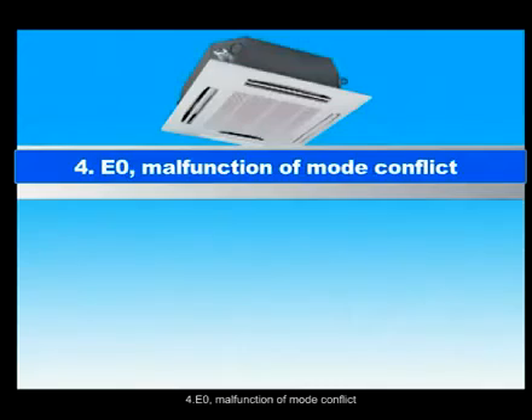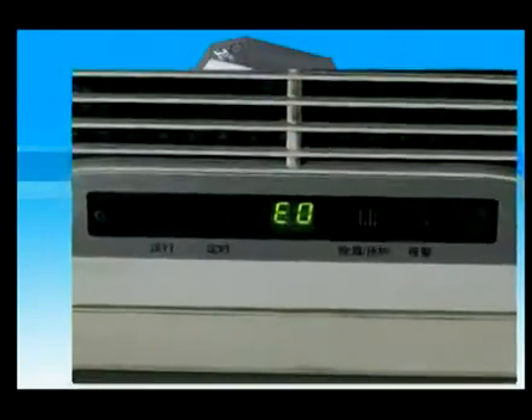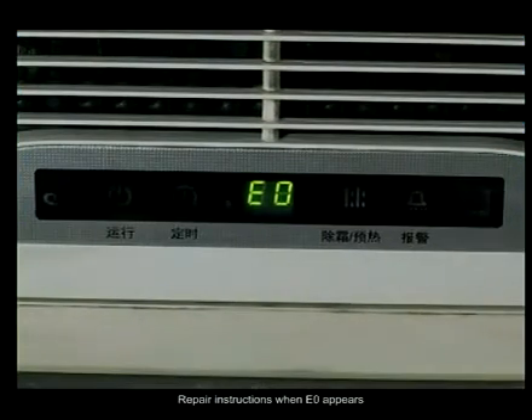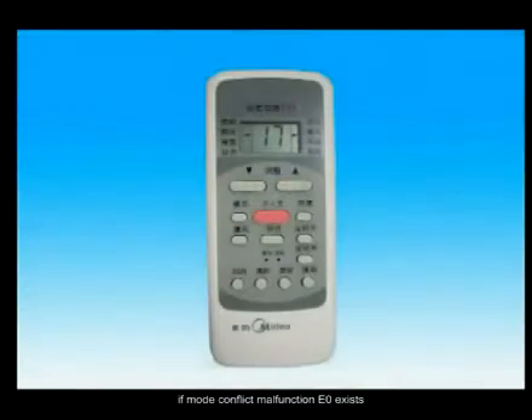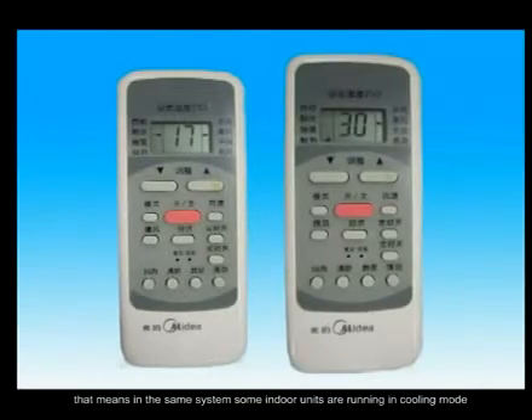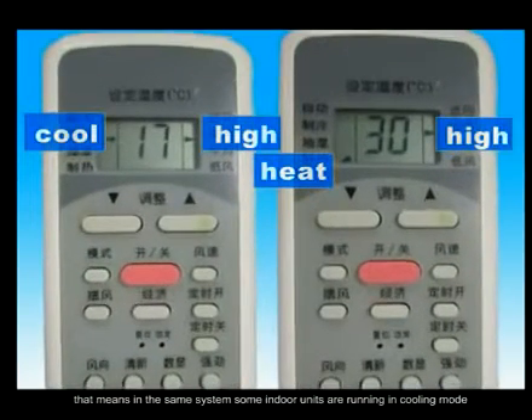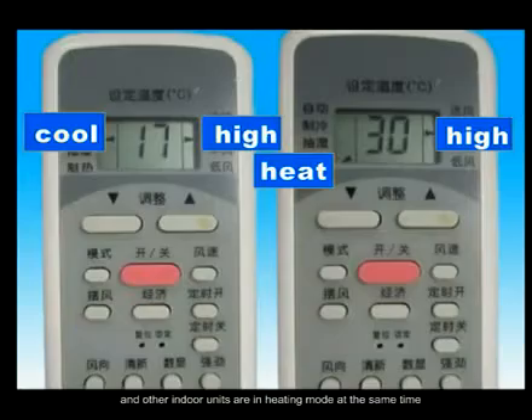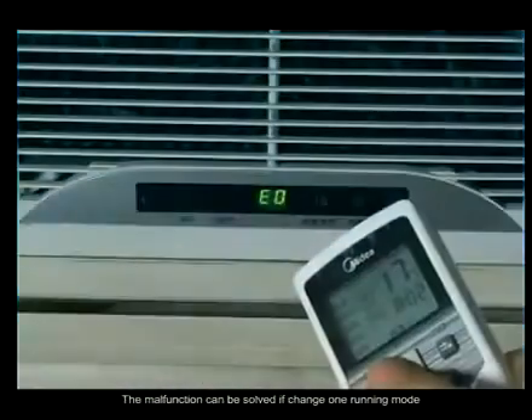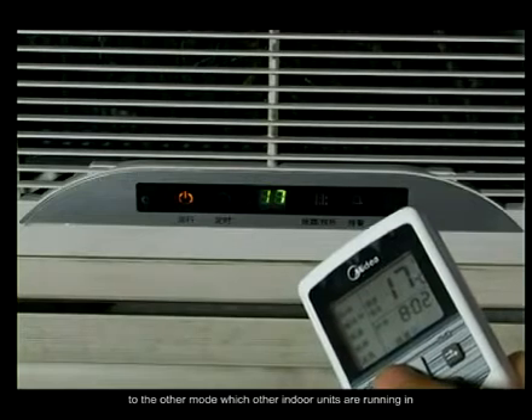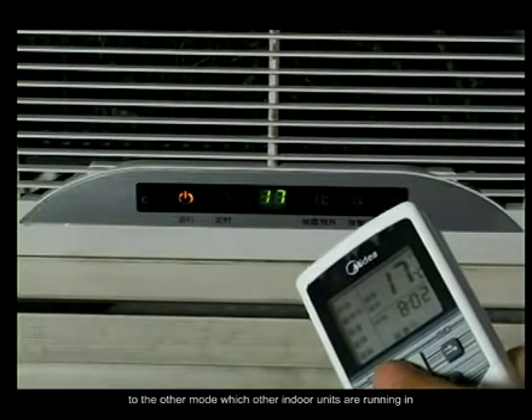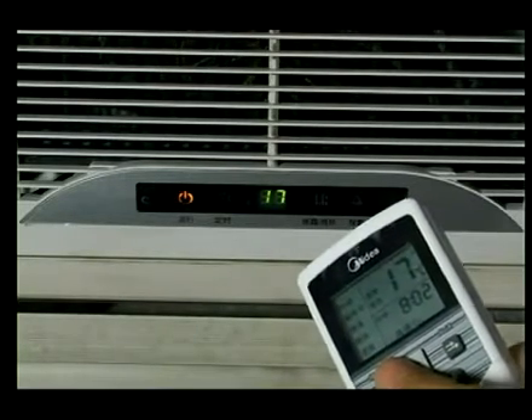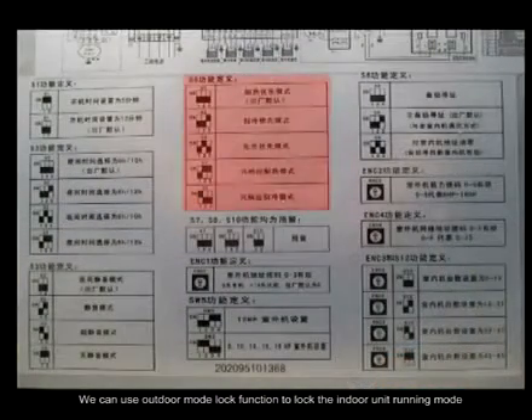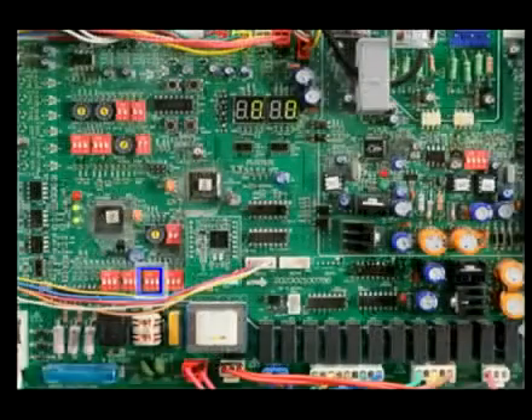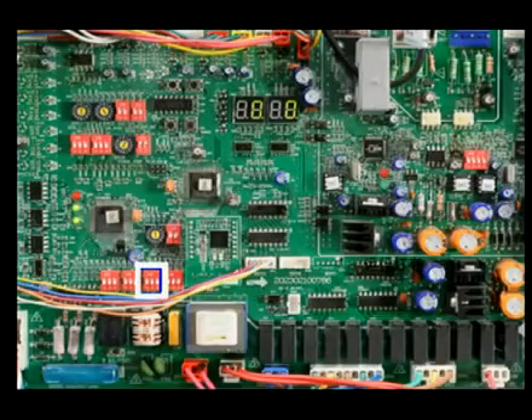4. E0, malfunction of mode conflict. Repair instructions when E0 appears. If mode conflict malfunction E0 exists, that means in the same system some indoor units are running in cooling mode and other indoor units are in heating mode at the same time. The malfunction can be solved by changing one running mode to the mode the other indoor units are running in. We can use the outdoor mode lock function to lock the indoor unit running mode. That will help the customers operate more conveniently.